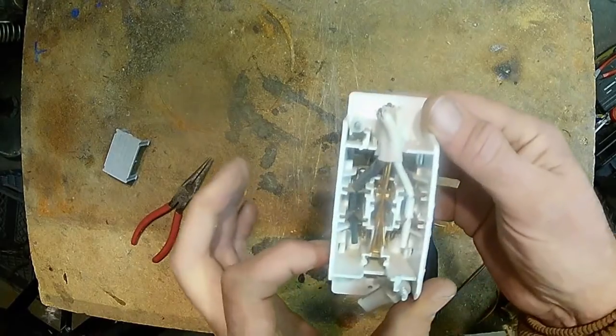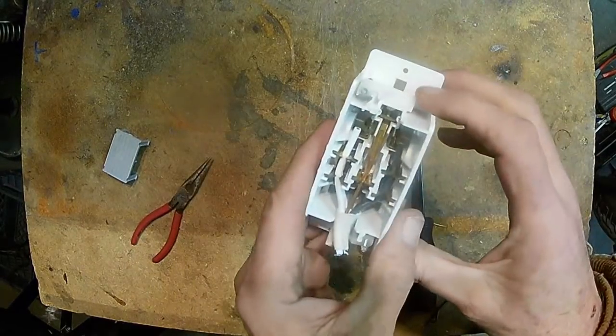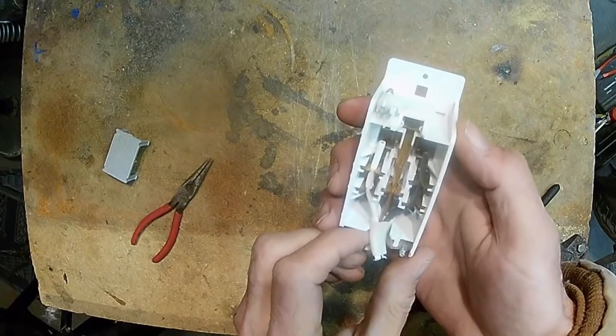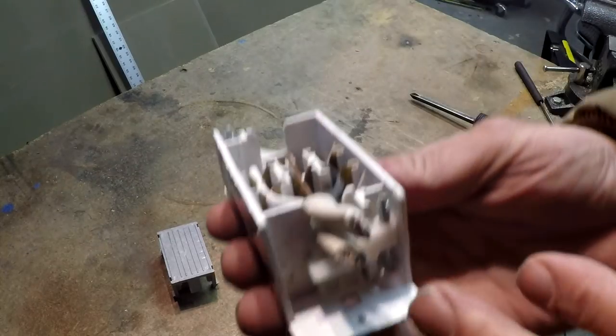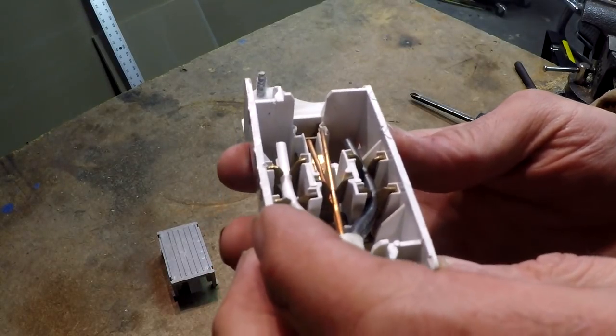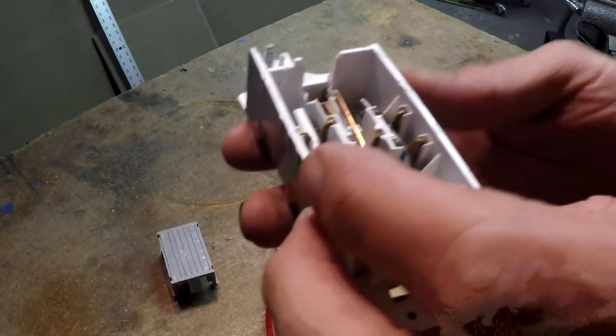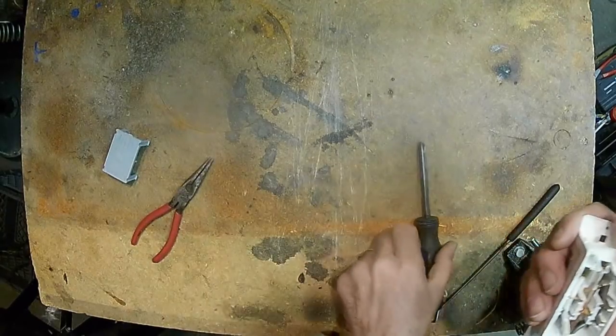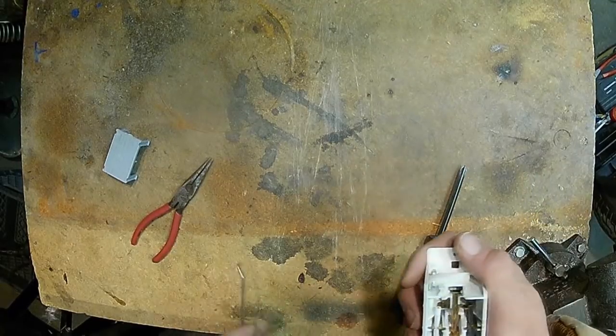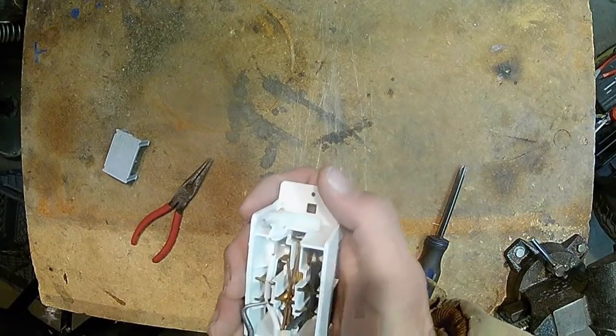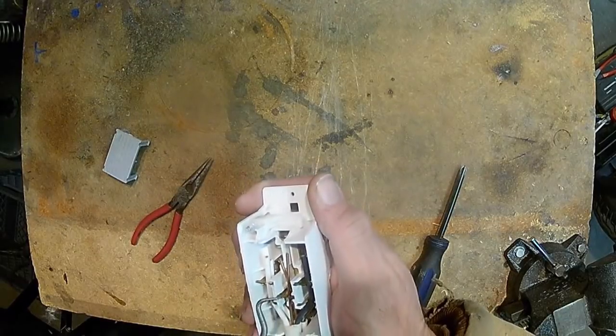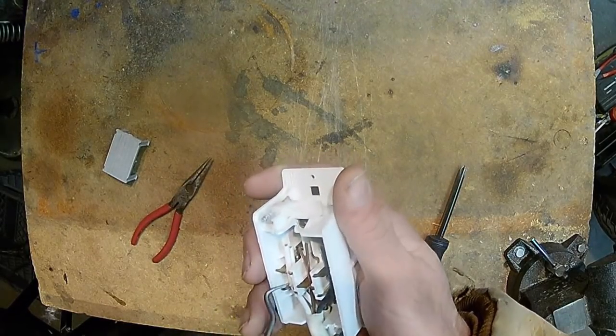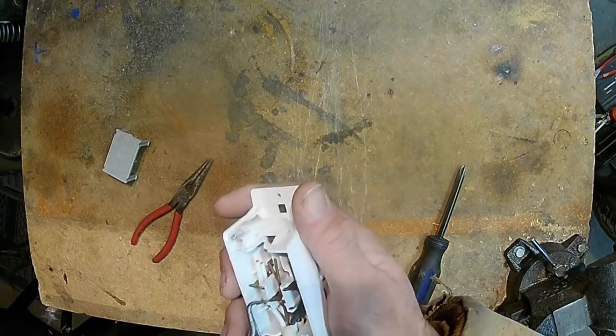Now the way these are manufactured, or designed, is that you actually just press the wire into the box, and that's what makes the connection. It's simple for installation, speed and everything like that. The problem is it does not give that good of a contact area from the wire to the actual outlet. So any heavy loads that are put on it is actually a stress.